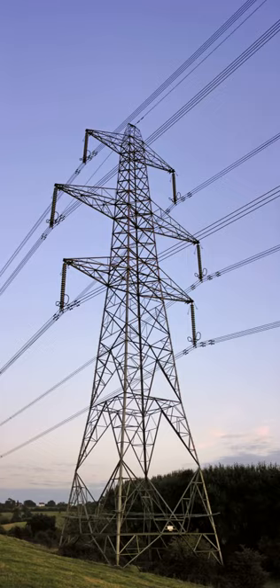If more than one circuit is required to be carried and the width of the line right-of-way does not permit multiple towers to be used, two or three circuits can be carried on the same tower using several levels of cross arms. Often multiple circuits are the same voltage, but mixed voltages can be found on some structures.